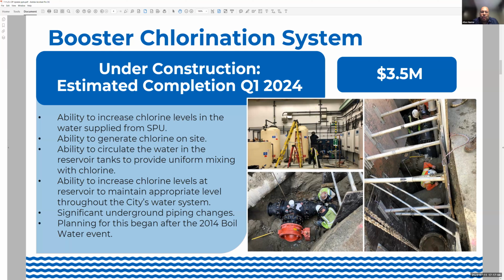Alan: Right now the chlorine levels in the reservoir are directly from SPU. Once this is online, we will have multiple areas to inject. We can inject at the inlet valves, we have two inlet valves that get water directly from SPU. The primary injection will be in the tanks themselves, so we can get 1.0 parts per million going out of the tanks to reach the parts of the distribution system. We also have a bypass where we can inject, as well as the canyon line, which we're running backwards down. If we ever had to use the canyon line as an emergency to receive water going up to the reservoir, we can also inject into the canyon line to get water from there.